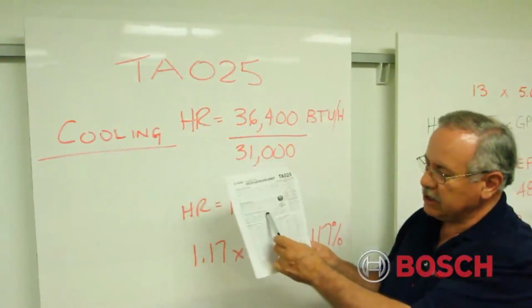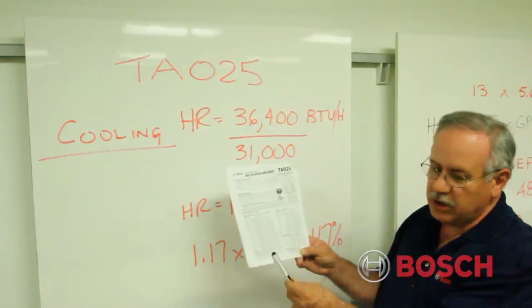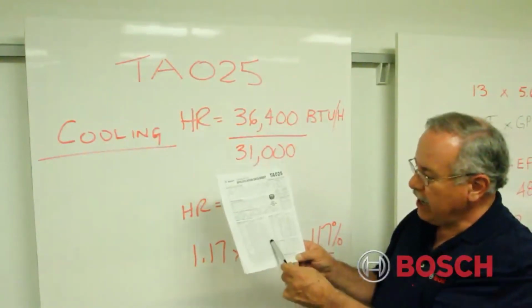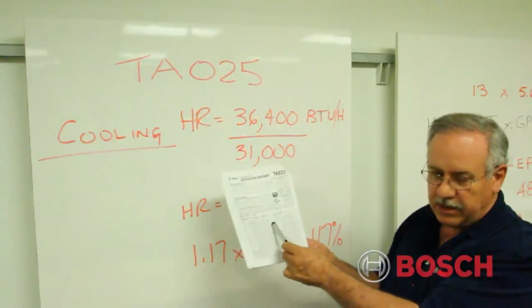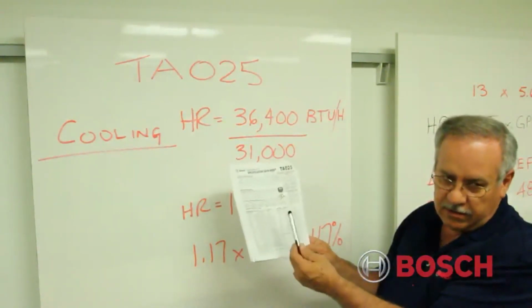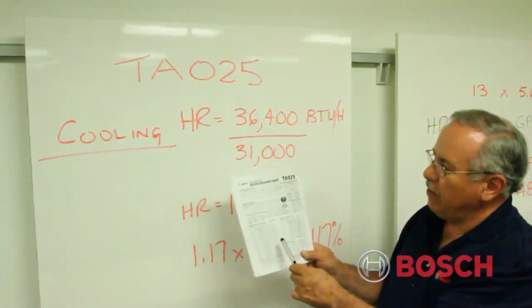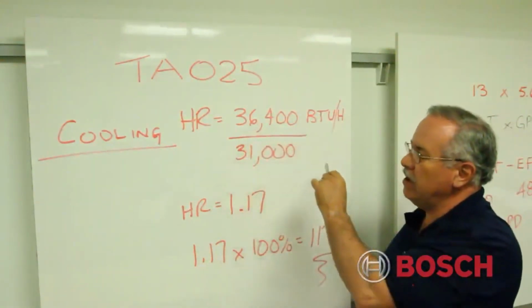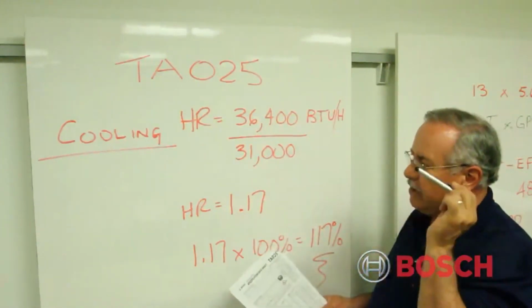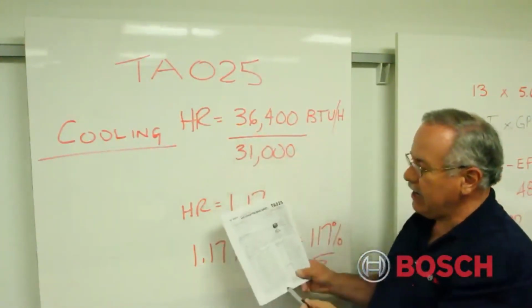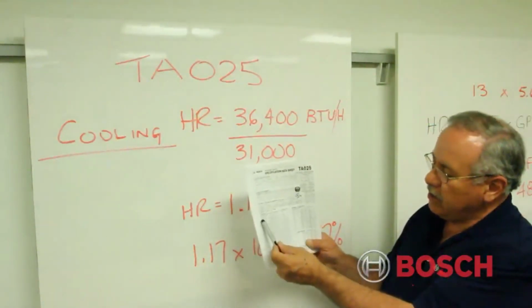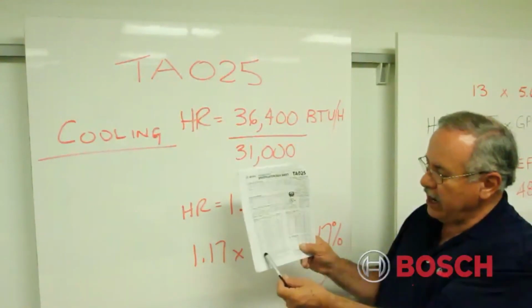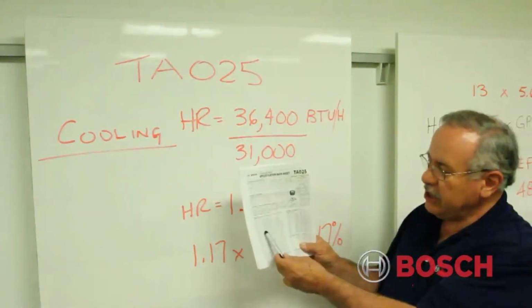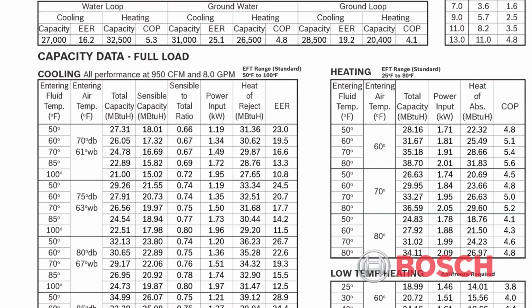Now we're talking about cooling, so we'll use this as the data to compare what we found against. Now if we had been in the heating mode, heat of absorption, we'd simply go to the right over here. Same formula, same calculation methods. So in our particular case, he determined 36,400 was actually being absorbed and rejected from the house into the earth.